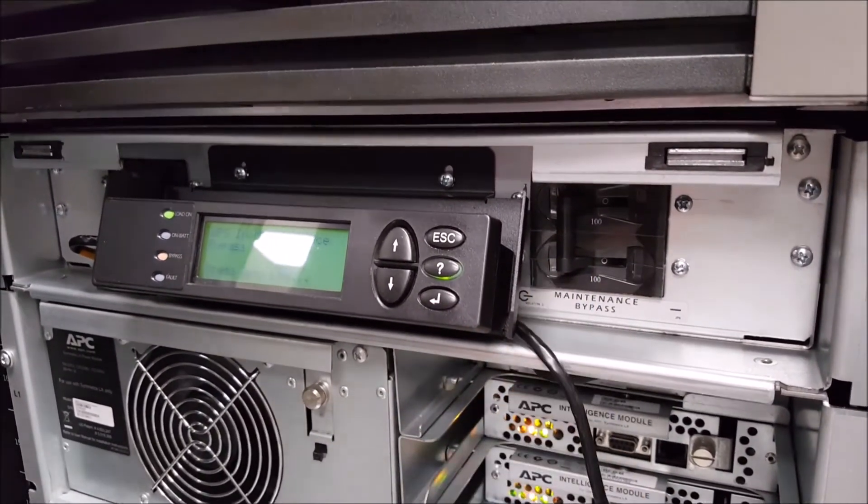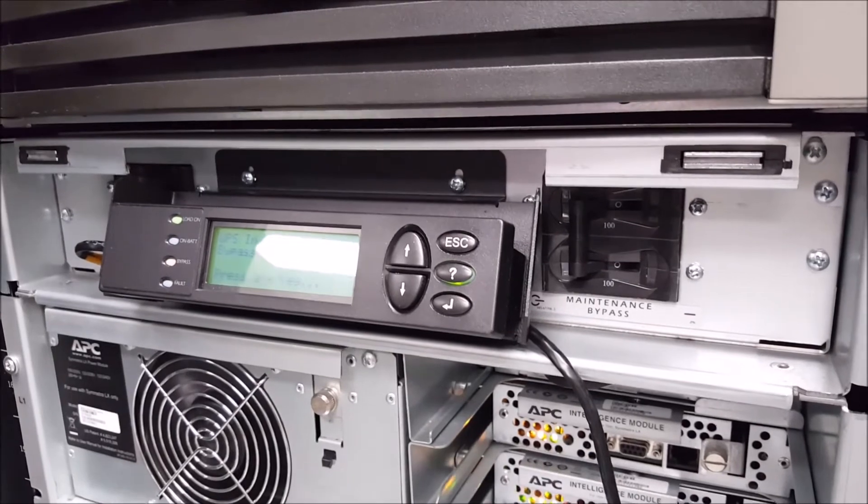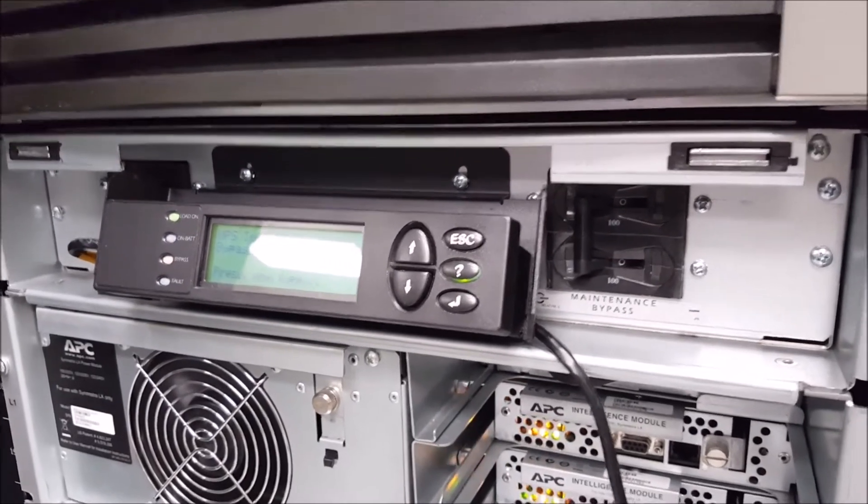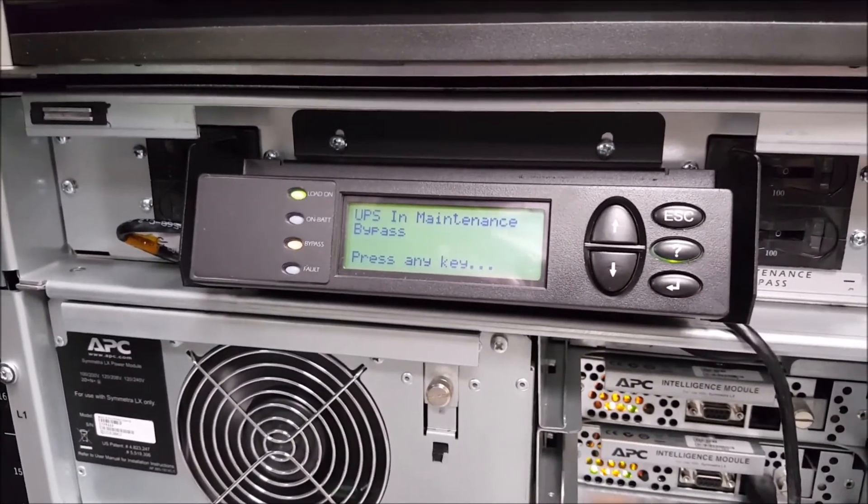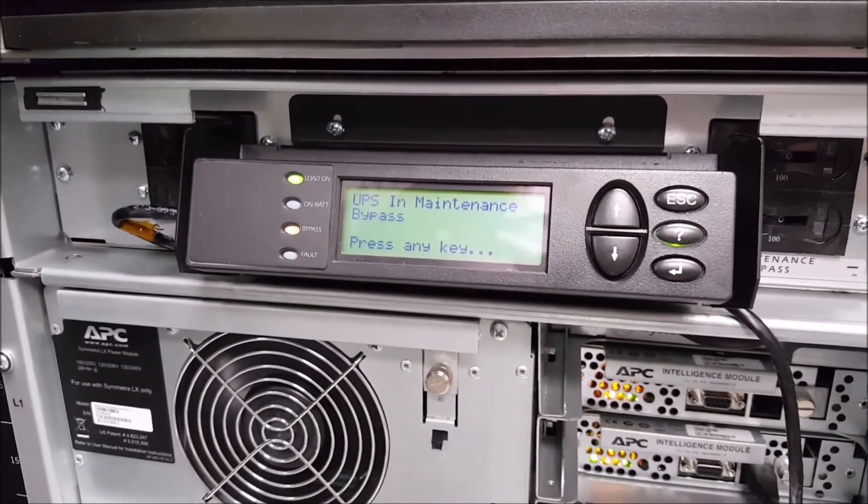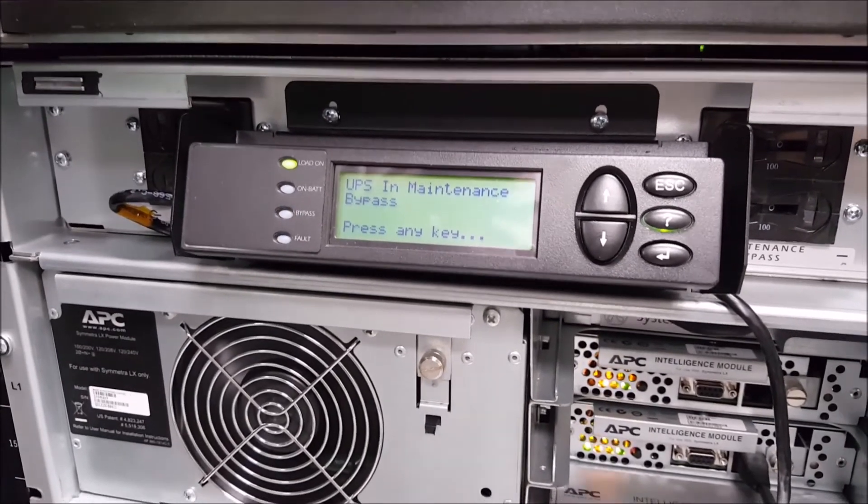Once the maintenance bypass switch has been disabled, you'll see the UPS come completely out of all bypasses. You do not need to disengage the logical bypass, and the unit may decide to run a brief self-test.